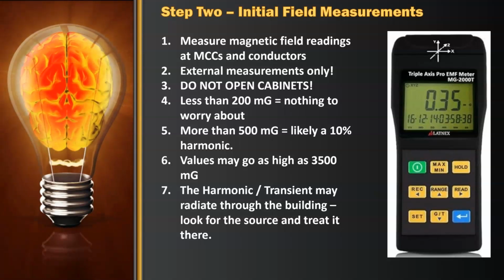Now what you're going to have to do when you find this is do some other checking on that MCC and see where that energy goes. Normally I start at the meter or the main transformer to see whether or not that energy is present there. If it's present there, I start working my way backwards through the MCCs to figure out which piece or pieces of equipment are causing a problem. I'm going to look for things like chillers, PV systems, inverters, and UPS devices. I'm also going to look at lighting systems, because LED lights tend to generate a fair amount of harmonics. Some of the cheaper ones do. And when I find those panels or devices, I'm going to isolate that and say, okay, the problem is likely here.